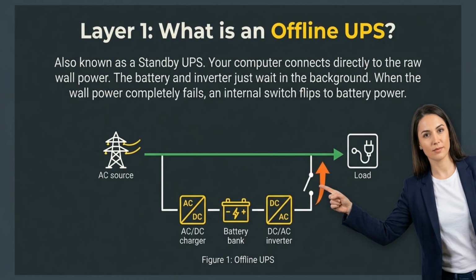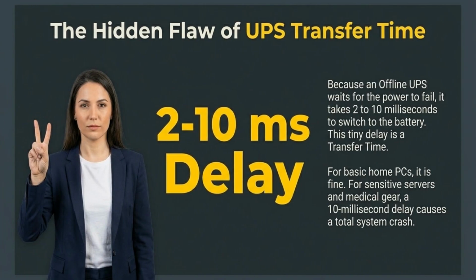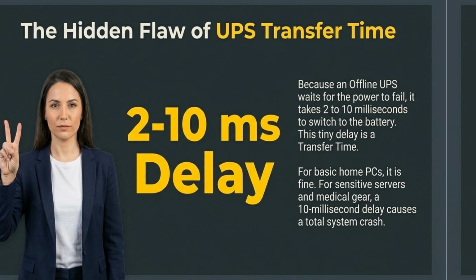Layer 1 is the offline UPS, also known as a standby UPS. Your computer connects directly to the wall power. The battery waits in the background, and an internal switch flips to battery power when the wall power fails. Because an offline UPS waits for the power to fail, it takes 2 to 10 milliseconds to switch to the battery. This tiny delay is called a transfer time. For sensitive servers, a 10 millisecond delay can cause a total system crash.